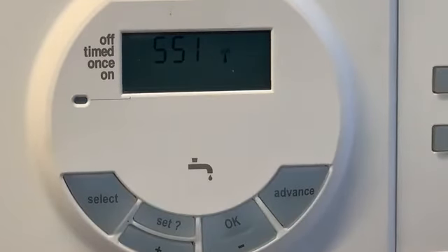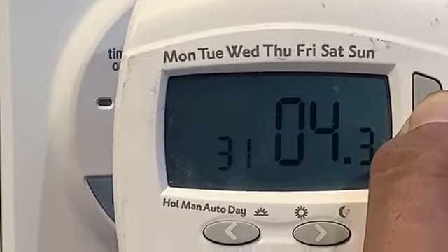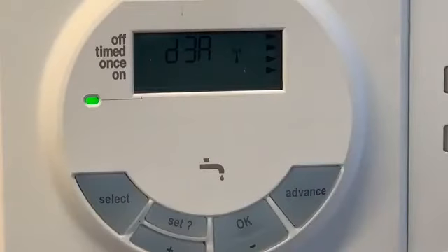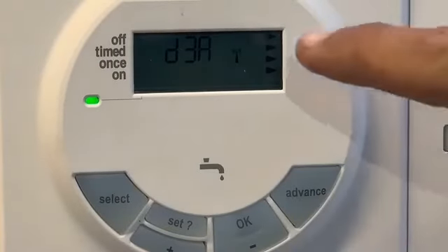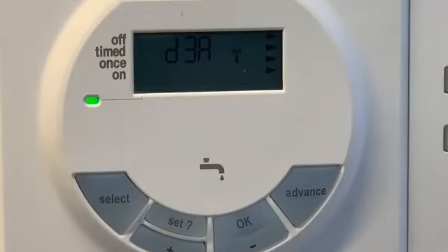you can then use the signal on the control itself with the batteries out. You press and hold. Let me try and get this into shot. Press and hold plus. Insert the batteries. Keep the plus button pressed down. That puts you into RF mode, and you can see now on the screen you've got 4 chevrons at the side. Those are a signal strength indicator. So if you now go off and put the control where you want it to be, you should see those chevrons change. So it's a good little indicator, rather than just adding the stat and just hoping for the best.